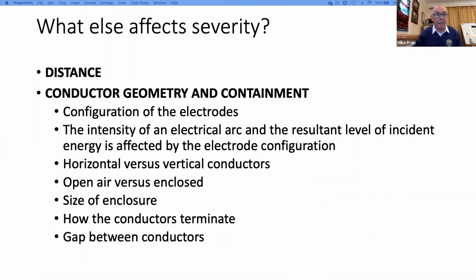So what else affects severity? Well, first of all, distance, and we'll talk a bit more about that. The relationship between distance and incident energy, it falls exponentially. It's a good reason to stay away and keep as much distance as a risk control measure. Secondly, the geometry, the conductor geometry and containment, in other words, is it in a box or is it in open air or whatever. So breaking that down, the configuration of the electrodes is important, the intensity of the electrical arc and the resultant level of incident energy. It's affected by the electrode configuration.